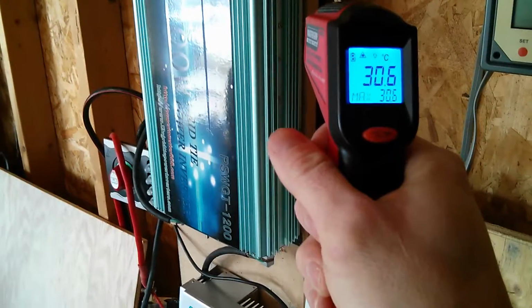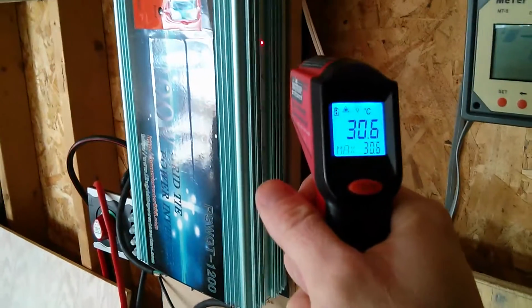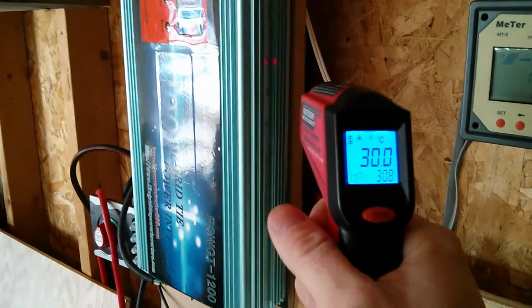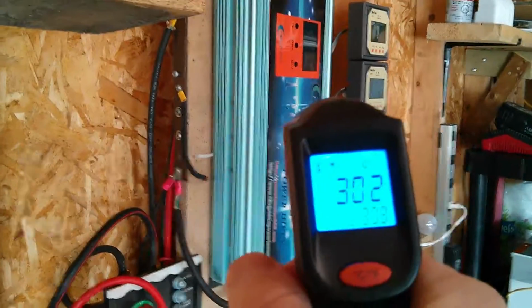22. Yeah, that's the hottest point, and that is right there where the laser's pointing. That's where they have the temperature module for the fans. That's where it's plugged in. So they did a good job on at least monitoring it where it is the hottest.